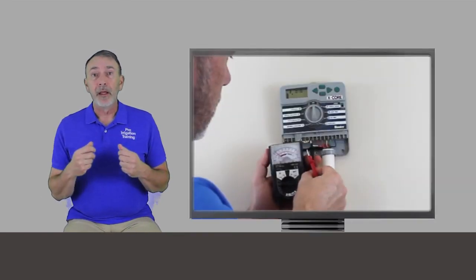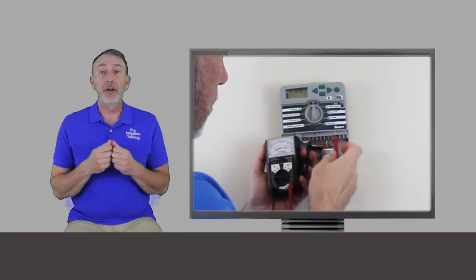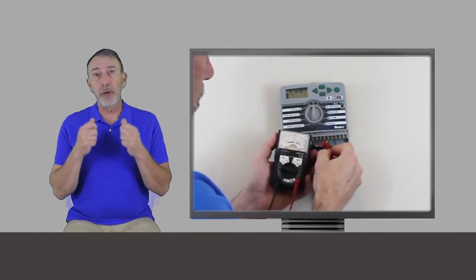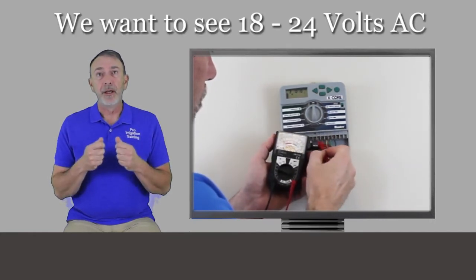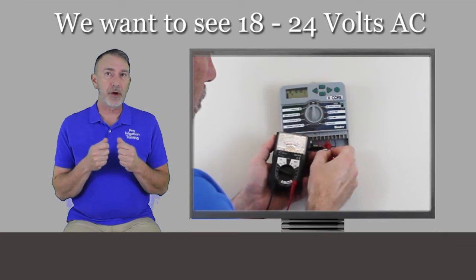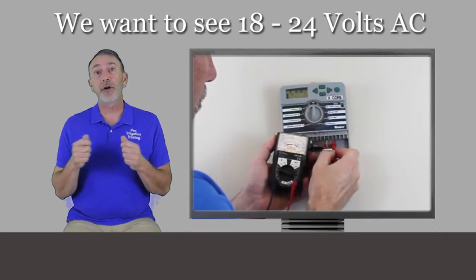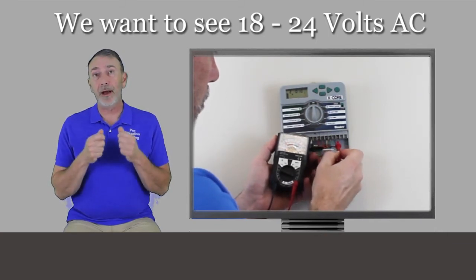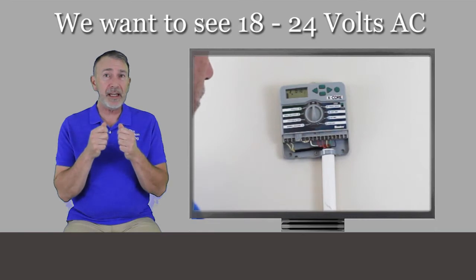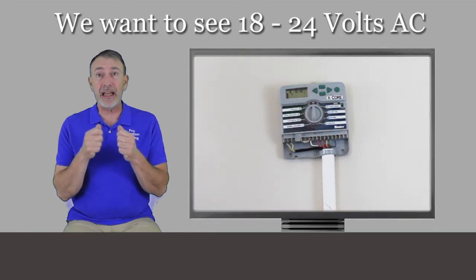Now, go back to the timer. While the zone is still on and running at the timer, use your multimeter to measure the voltage on that circuit and then check the rest of the circuits as well. If you get any voltage on any of the other circuits that shouldn't be running, then there can be two problems happening. Either the timer has a problem inside of it or there's wires touching out in the field or somehow otherwise allowing voltage to be fed back through the other zone wires.